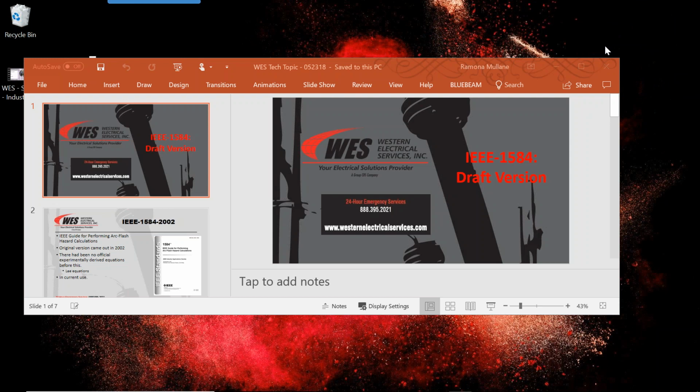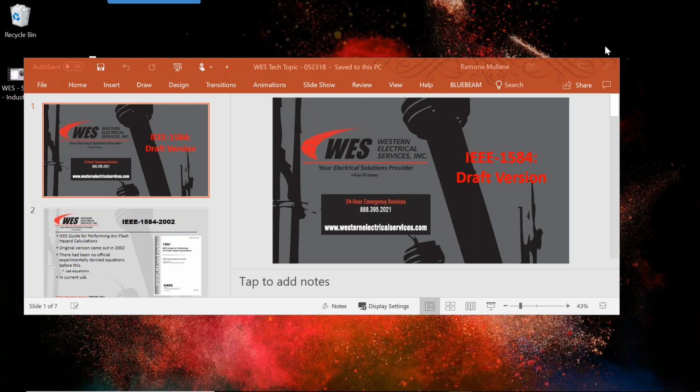Secondly, the more important comment I had for them was, look at where the exhaust actually exits the building. For posting purposes, it had a very, very small sign that said, oh, by the way, hot gases could come out of here. That was it. Having said that, I recommended that the area be properly bounded off during any switching or racking operations to preclude individuals from being in the area in the event of a fault, and more importantly, improve their warning systems, since the area under normal circumstances could become a danger zone. It was pointed out and they've taken action.